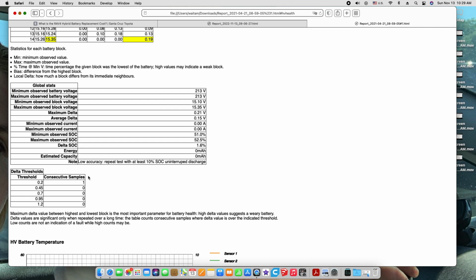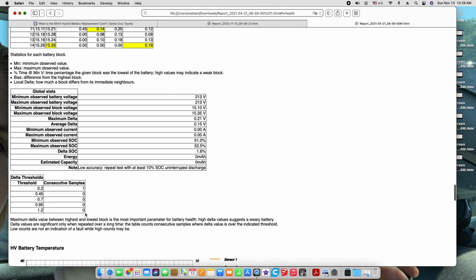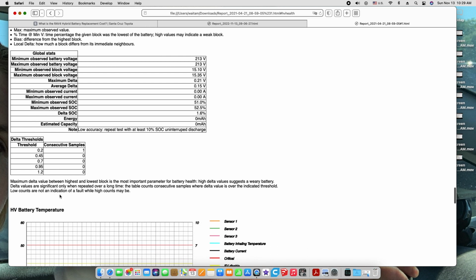So they take a sample, and if the voltage delta is at a minimum, it'll tell you 0.2, so one time. But if you keep getting 1.2 for many times, then you know your pack has a problem, because that's the maximum voltage difference between the highest block and the lowest block.